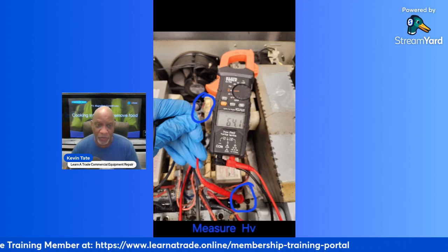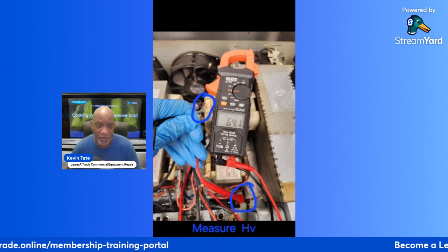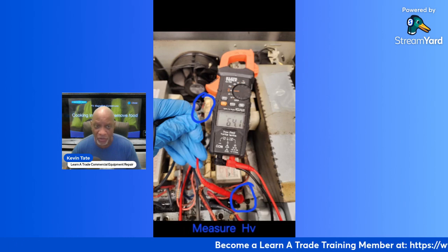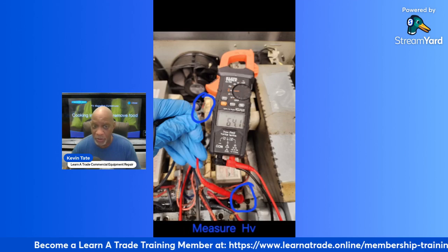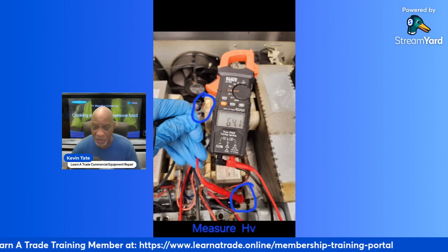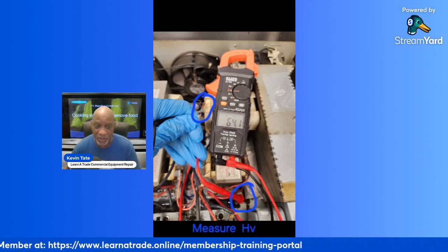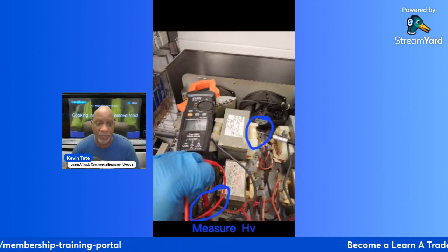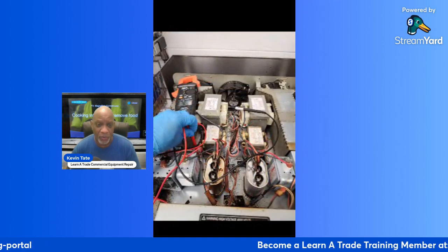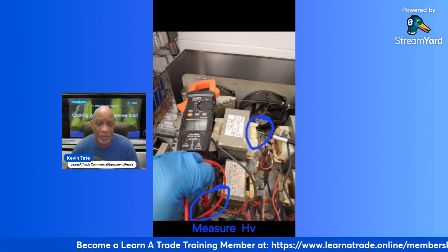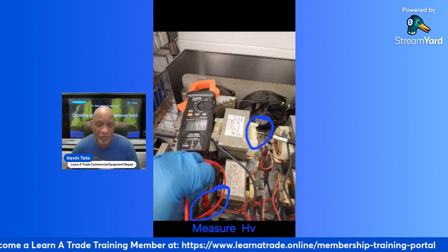But if you test out your terminal 4 to ground and you have a good reading, then more than likely you're good to go, unless you see that there's like burn damage on the transformer. If you see any burn damage on the transformer, you should definitely replace that transformer. And then next, I always check, let me go back here. Sorry about that. Right here, I always check both transformers.